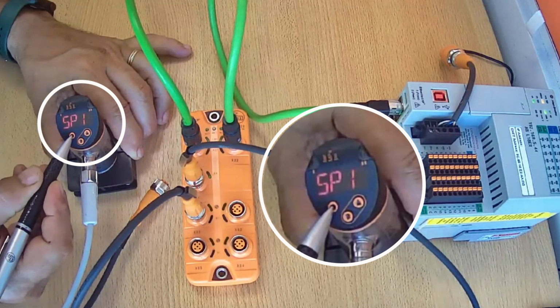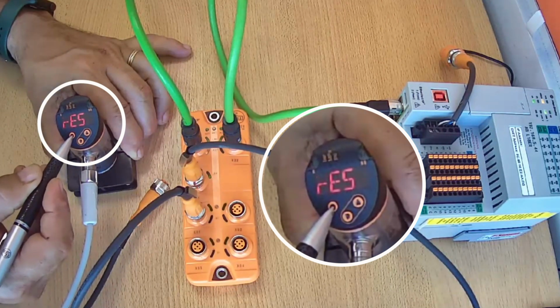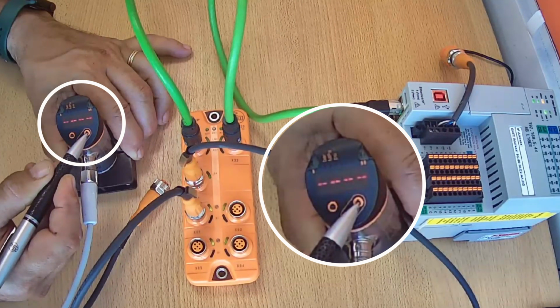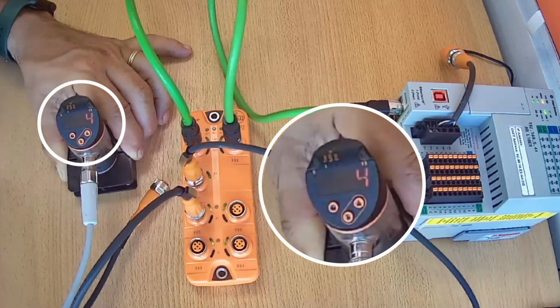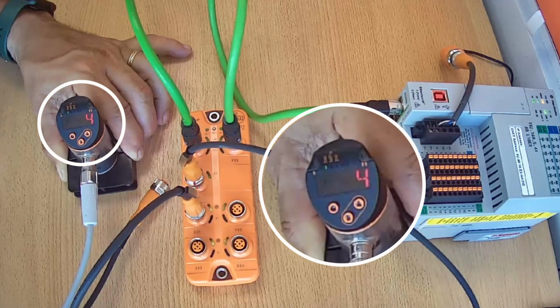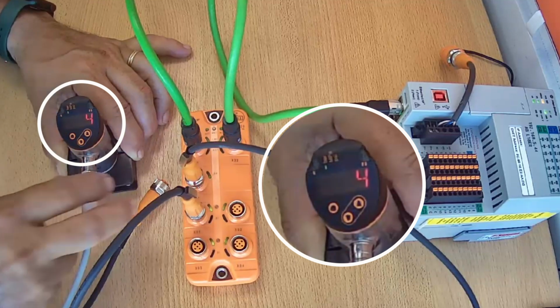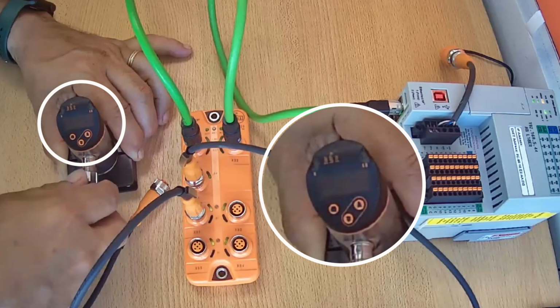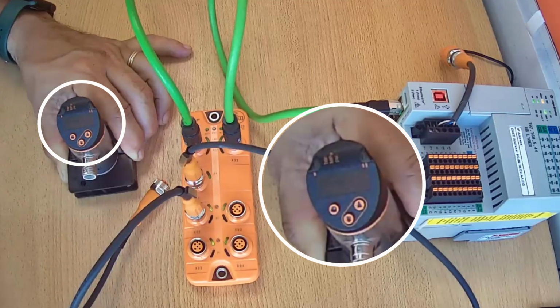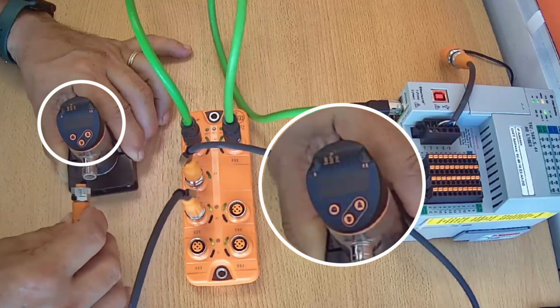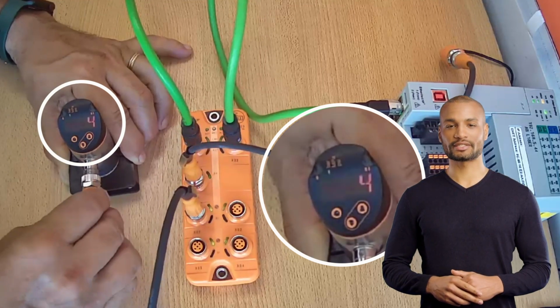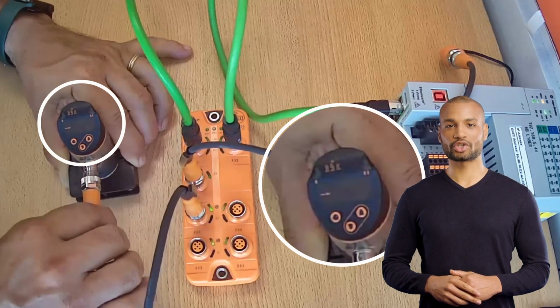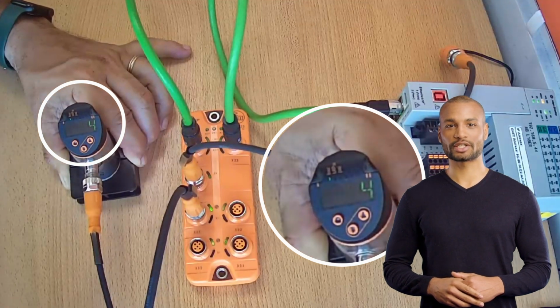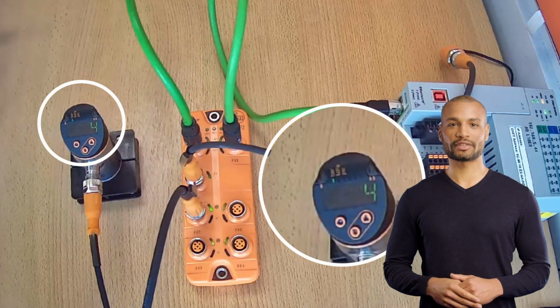As we can see, the sensor display is red by default. Now we connect exactly this sensor to the IO link port of the master we have configured and see what happens. The master recognizes that it is a factory set device and overwrites the saved parameter set. When the transfer is successful, the sensor display turns green. The new pressure sensor is now parameterized in the same way as the previous device.